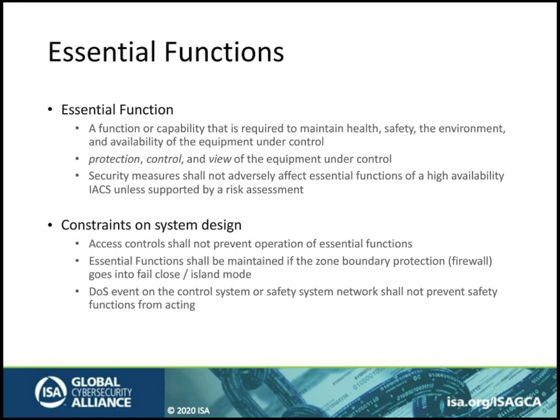The concept here is that security measures shall not adversely affect an essential function. For example, if you have a big red push button to shut down the process, and you have a software version of that, you wouldn't want to require a login before you can initiate the emergency shutdown function. That's essentially what we're talking about for essential functions.